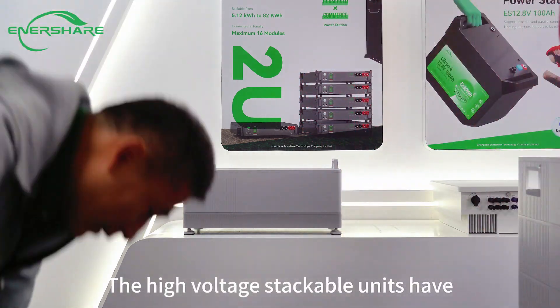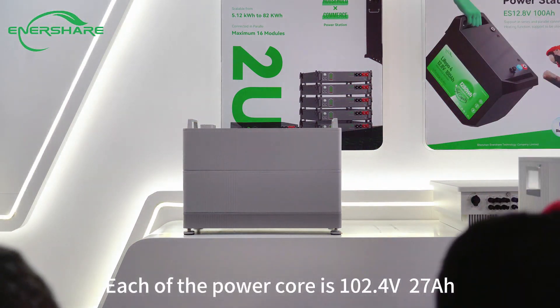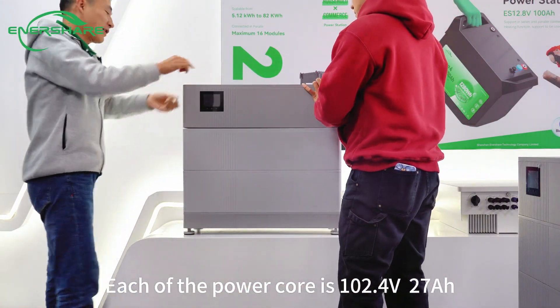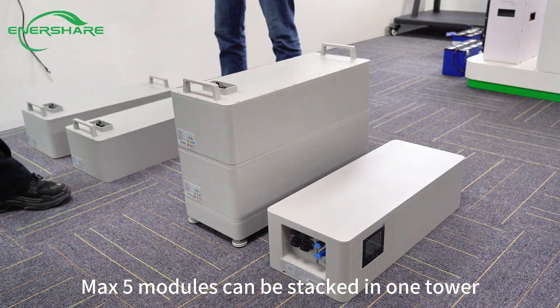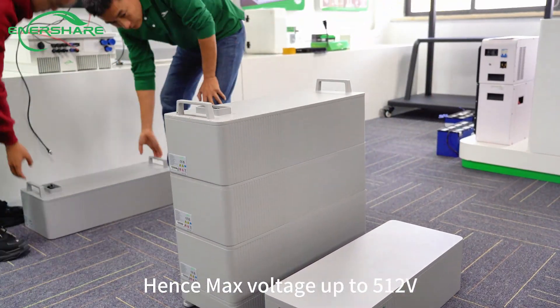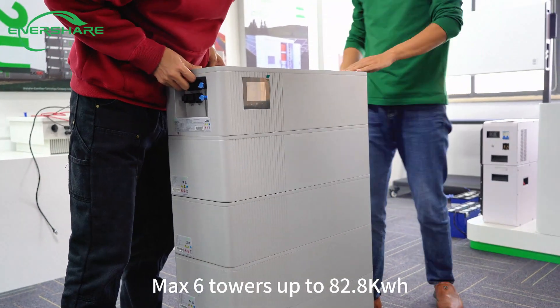The high-voltage stackable units have direct connection — no additional wires, no additional screws. Each Powercore is 102.4 volt, 27 amp-hours. Each uses prismatic lithium-ion cells. A maximum of five modules can be stacked in one tower, giving a maximum voltage of 512 volts. Following that, up to six towers can be connected in parallel, up to 82.8 kilowatt-hours.